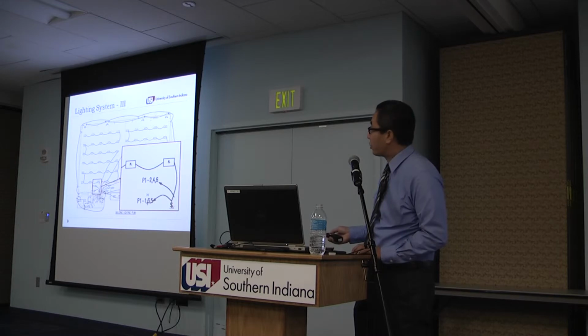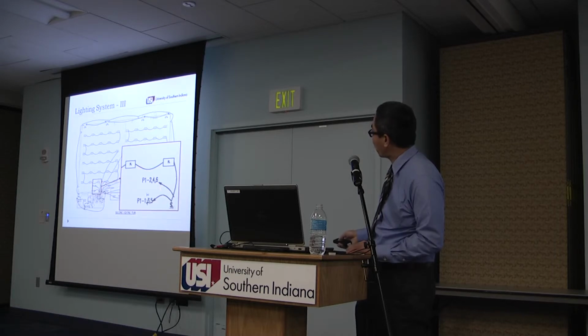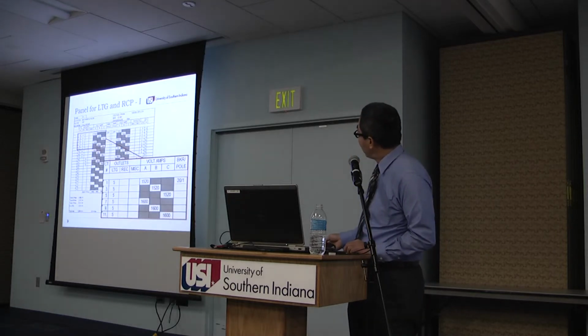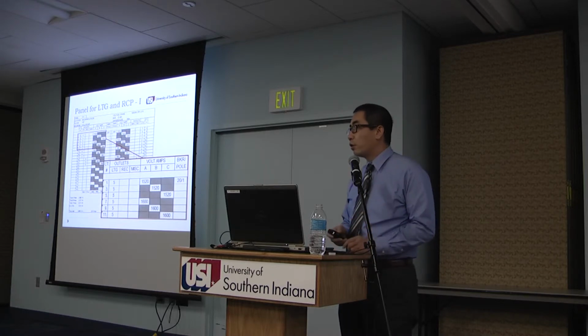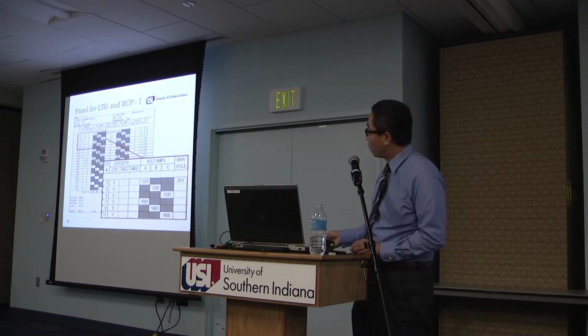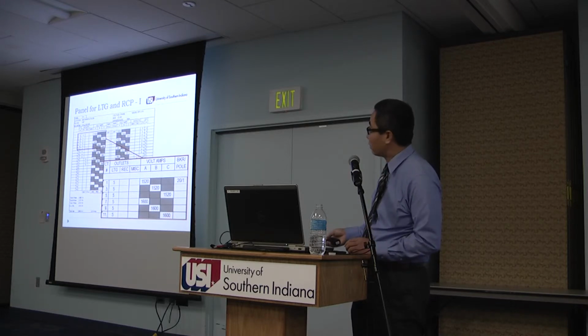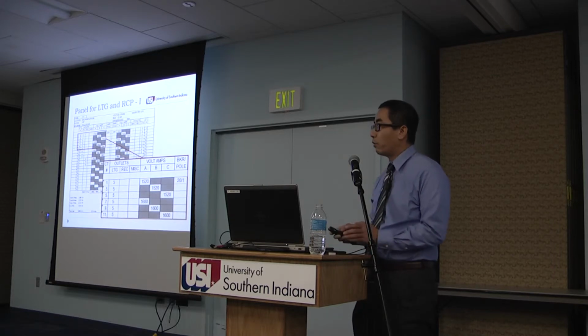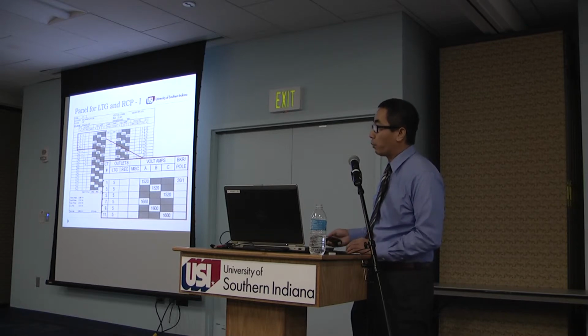Again, we need to tie all the lighting fixtures together, making sure we don't exceed the circuit capacity. And here's how we run the circuit back to the panel. Again, this is the fluorescent lighting. We tie to the switch, and this is the home run back to the panel. We use a single panel for all the receptacle and lighting load. And here's the enlarged portion of the lighting panel. The first column, the circuit number, is the one we just saw on the layout drawing. And that's how many lighting fixtures are on that circuit, and how many volt-amps per circuit. We're trying to balance them, so all three phases are roughly equal. You don't want to heavily load one phase, and then have a large neutral current coming back to the panel.